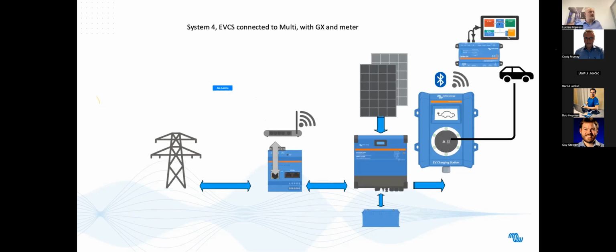The last configuration is the most complex. Of course this diagram is simplified - you can have 3-phase, and the PV inverter or PV panels can be DC coupled. You can have multiple configurations like this, but this is the simplified version. By doing so you get all the functionalities from before, but the charging station can also stop based on the state of charge of the backup battery. This system can also switch to off-grid mode, so it works the same but without the grid - it can be used off-grid or with a generator, giving all the functionality discussed before.